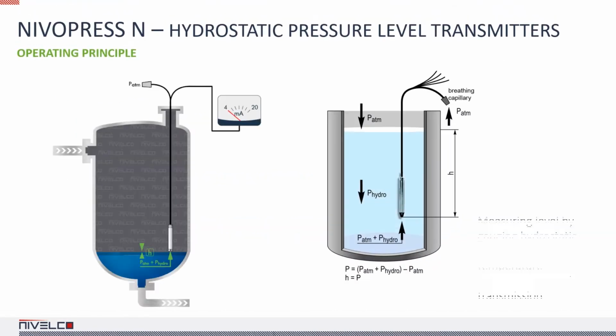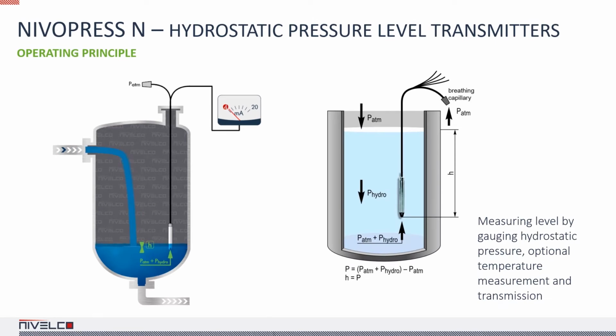On the other hand, NIVOPRESS N hydrostatic level transmitters are designed to measure the level of clean and contaminated liquids. The pressure sensor at the bottom of the probe measures the sum of the atmospheric pressure and the hydrostatic pressure of the liquid column. The atmospheric pressure is channeled to the sensor through a breathing capillary equipped with a moisture filter that prevents moisture from damaging the electronics. The atmospheric pressure is subtracted from the overall measured pressure to get the hydrostatic pressure, which is proportional to the height of the liquid column. Then the sensor signal is converted into an output signal.